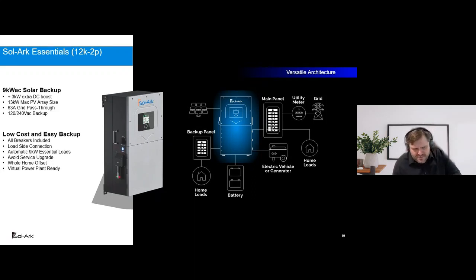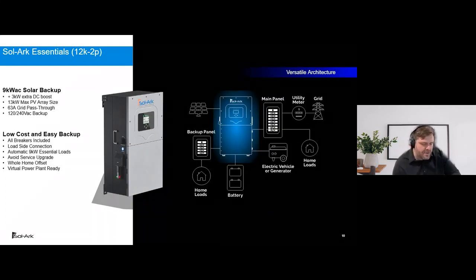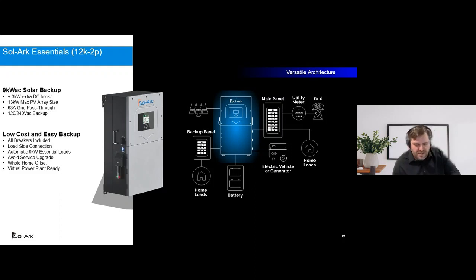David, on your 400 amp service question, I would actually combine the two Sol-Arks together and even look into a 400 amp main lug only panel, do the whole house on a 400 amp panel rather than two 200 amp panels. Now, two 200 amp panels is common, and you can do that with a Sol-Ark, but you could keep the two 200 amp panels and put in a combiner, or you can feed the panels individually.